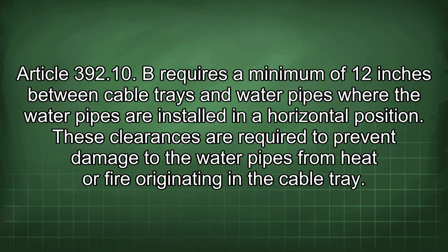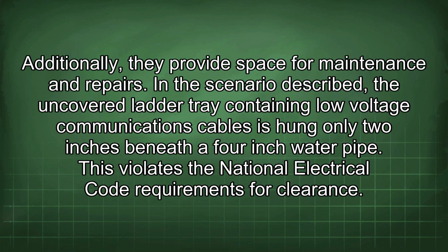These clearances are required to prevent damage to the water pipes from heat or fire originating in the cable tray. Additionally, they provide space for maintenance and repairs. In the scenario described, the uncovered ladder tray containing low-voltage communications cables is hung only 2 inches beneath a 4-inch water pipe. This violates the National Electrical Code requirements for clearance.